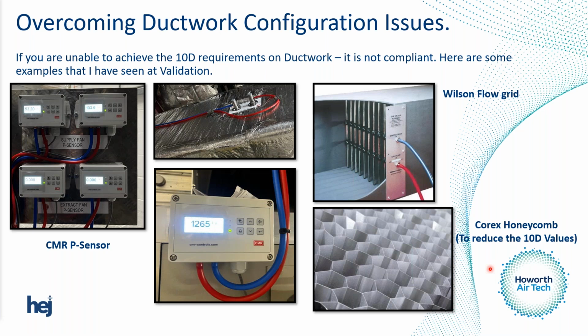Have seen it in practice with Zeal. I was talking to them last week about an axial fan for an air handling unit, and they put a Corex honeycomb across the intake section of the fan, and they believe that it makes it more laminar and takes some design noise out of the fan. So that it is in use. I've just never seen it in use inside the duct, but I thought I'd mention it because it's on that course.